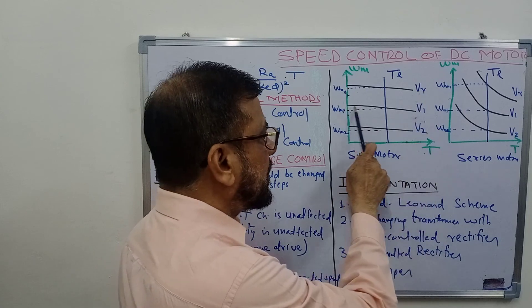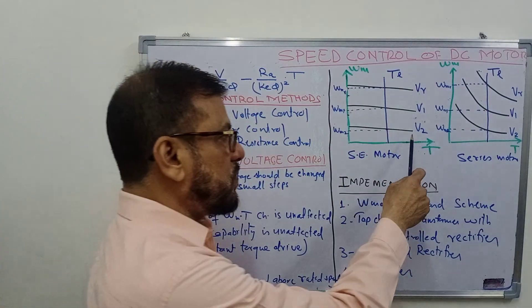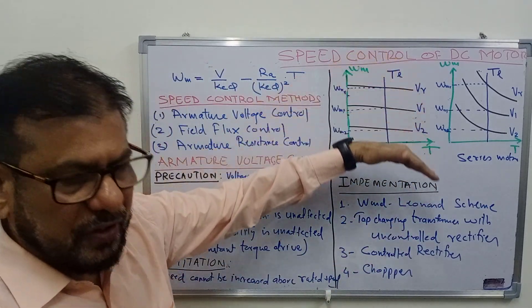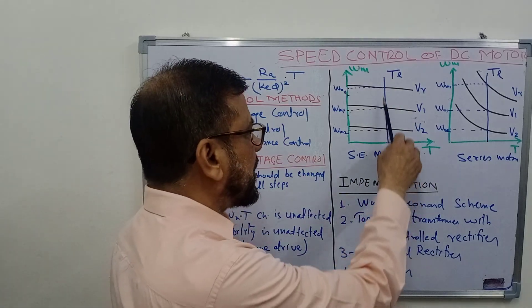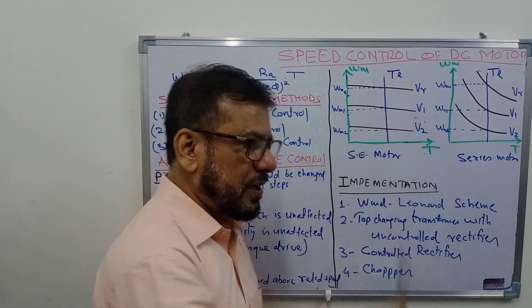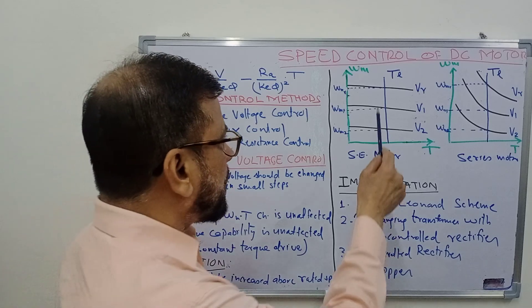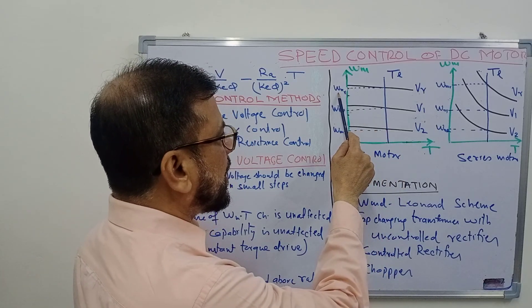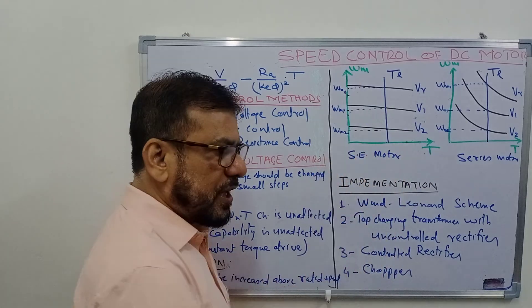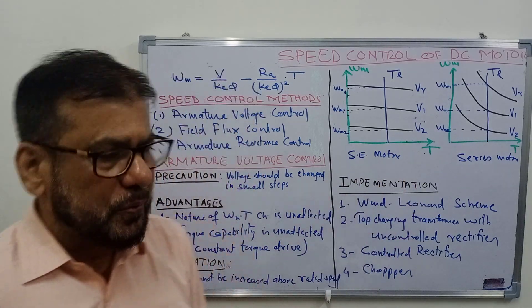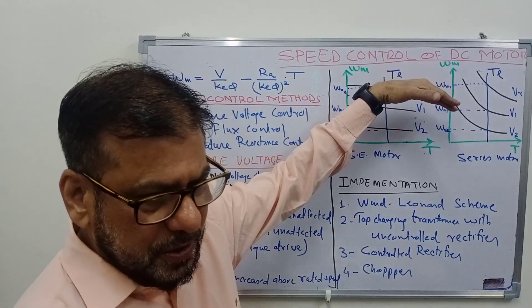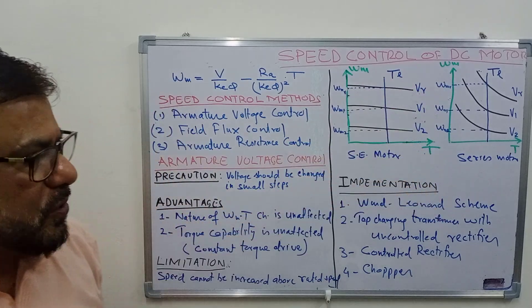For V1 less than VR and V2 less than V1, the characteristics shift parallel to themselves. For a constant torque load, the intersection of the load and motor characteristics gives the operating point. At rated voltage the speed is ωmR, at voltage V1 the speed is ωm1, and at V2 the speed is ωm2. So you can vary the speed over the whole range from rated speed down to a very low speed close to zero.